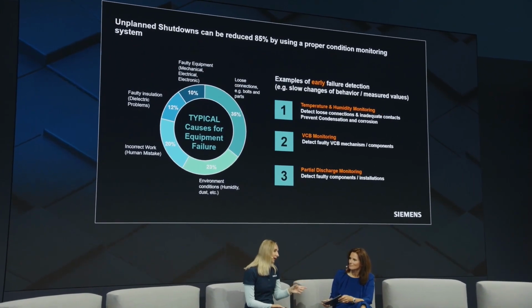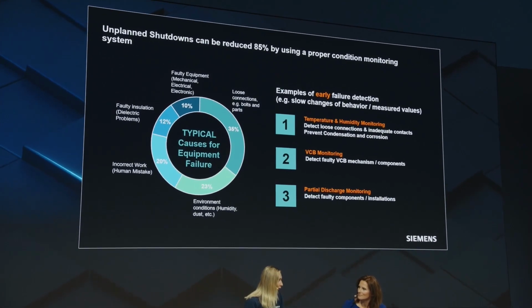And with this we can prevent power outages. That's one part. The second part is the so-called circuit breaker monitoring. The circuit breaker is the most important component within a switchgear, so also here we provide a monitoring for it. We look at, for example, the opening and closing times, the current during switching operation, the motor of the circuit breaker and so on.